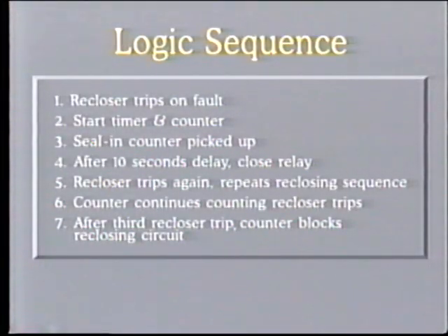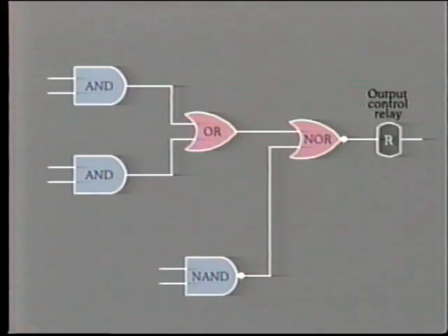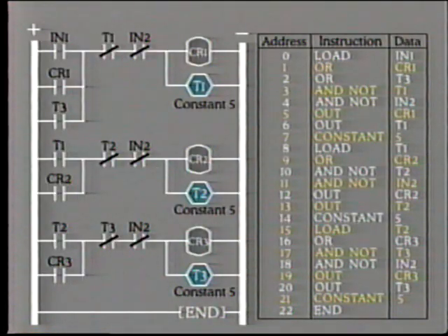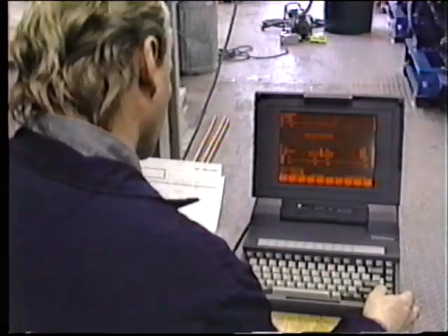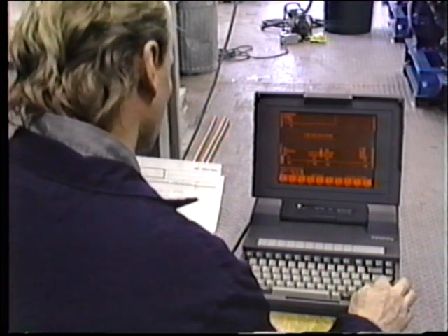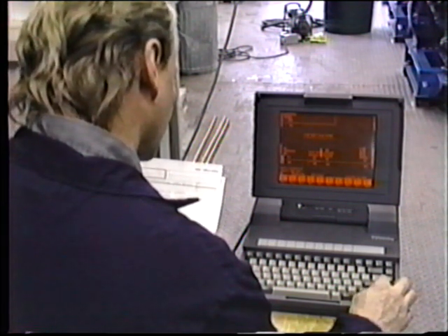As we've noted before, program logic instructions can be prepared in several different forms. First, we could have a series of written statements indicating the sequence of conditions required to energize each specific output contact. Another method is to prepare a logic diagram using logic gate symbols. The third and most common method is to use a ladder diagram representing electrical contacts and functions. Many PLC programmers allow us to input written instructions by pressing the appropriate buttons.